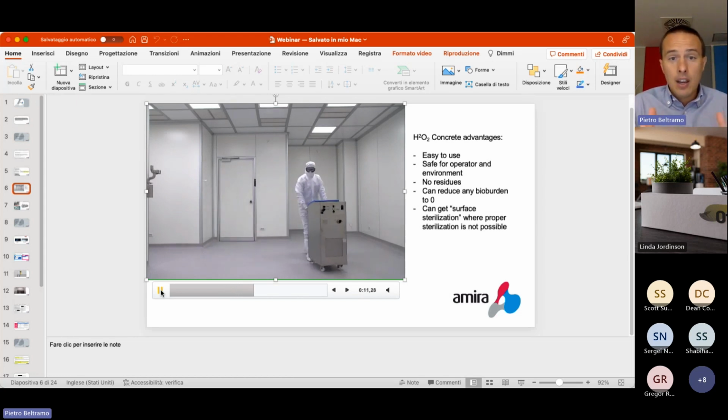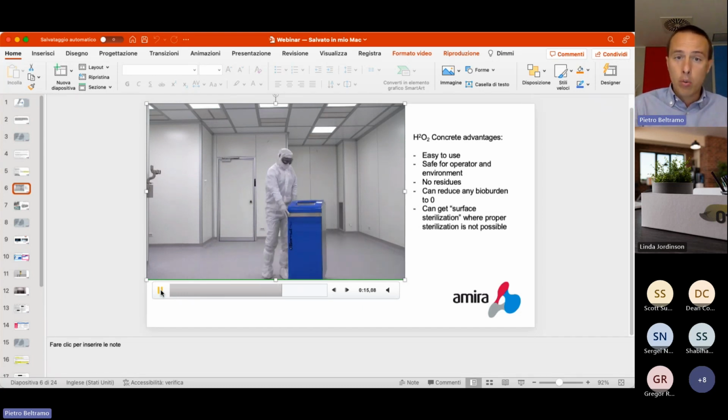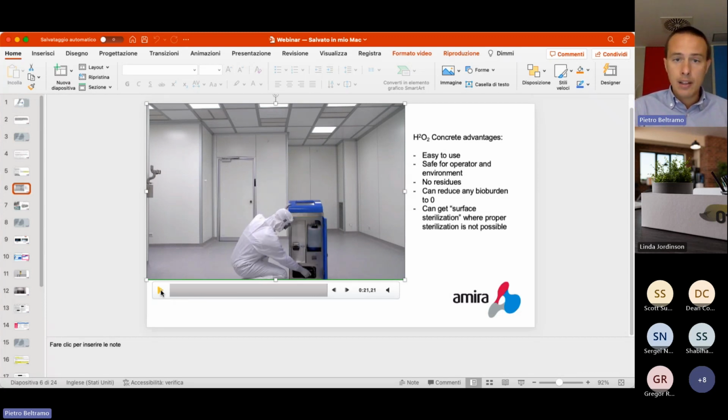It's pretty simple. You take the VHP generator, you bring it into the room, you take out a power plug, you connect it to the building, and you start decontamination. We will see an actual decontamination in the next video. With that simple operation, you can get a surface sterilization, for example in a room where another kind of sterilization is actually not possible, because you cannot put the room into an autoclave. But the H2O2 vapor can get the killing, can get the sterilization, can get to ground zero on your microbiological contamination, can get the biodecontamination done in your specific application.